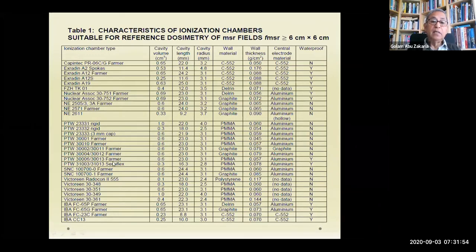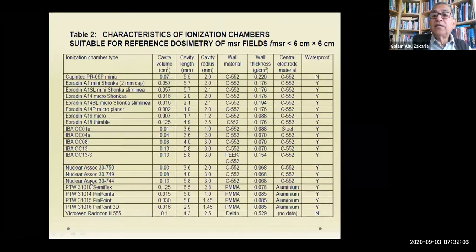You can use this chamber because the field is larger, and to measure the dose with such types of chamber, you have an equilibrium in the central position. That's why it is the normal way. And you see here the next table, when the field is less than 6 by 6, you select one of these chambers here. Yeah, you know the very important chamber is the pinpoint chamber. But in this dosimetry, you should select any ionization chamber. And these are the values given here. Yeah, you see here the volume is very, very tiny because you want to measure the small field.